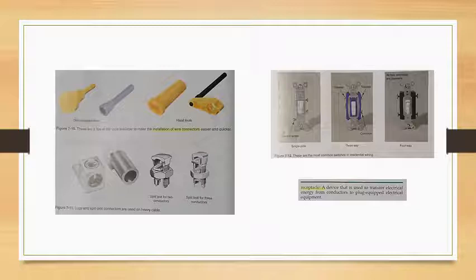Other methods of joining wire. Besides previously discussed methods of joining wire, joints can be secured with other metal connectors such as bolt-on lugs, split bolt connectors, compression connectors, and compression lugs. These types are used to join heavy wires such as 6 AWG or larger. The compression terminations are made with a special crimping tool. When using any of these items, always wrap all exposed metal with rubber or plastic tape to a thickness equal to the conductor's insulation.